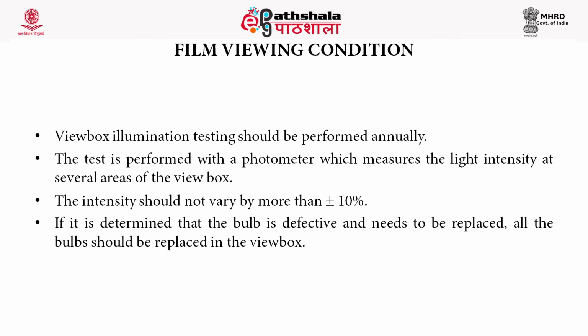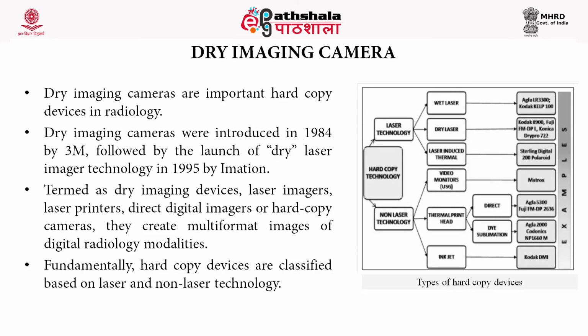Dry imaging cameras are also used in the Department of Radiology. Dry imaging cameras were introduced in 1984 by the company 3M, followed by the launch of dry laser imager technology in 1995 by Imation. Termed as dry imaging devices, laser imagers, laser printers, direct digital imagers or hard copy cameras, they create multi-format images of digital radiology modalities.